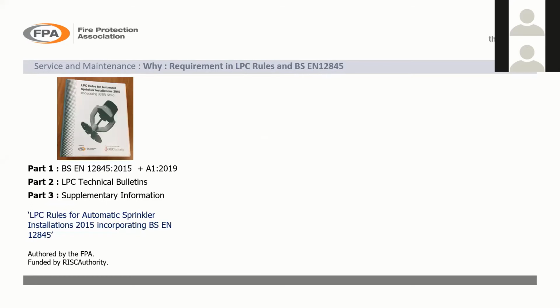The systems which have been designed to the LPC rules, it's a requirement that they are maintained, obviously, and Parts 1 and 2 are where these requirements come from. If you're not familiar with the LPC rules, BS EN 12845 is a standalone standard which specifies the design and installation of sprinkler systems. And then Part 2 is the LPC technical bulletins, which are issued by the FPA and written by RISCAuthority in association with the insurers. Part 3 of that document is just some supplementary information, which we won't cover today.